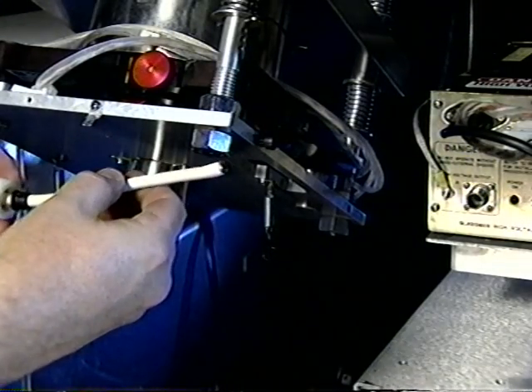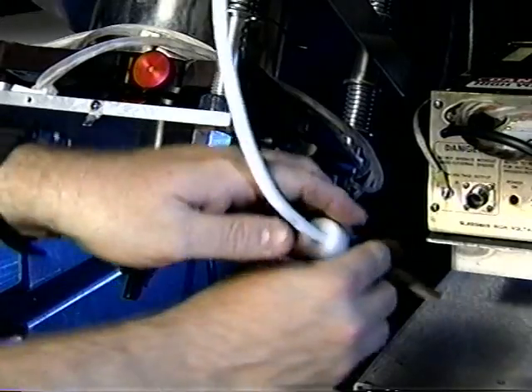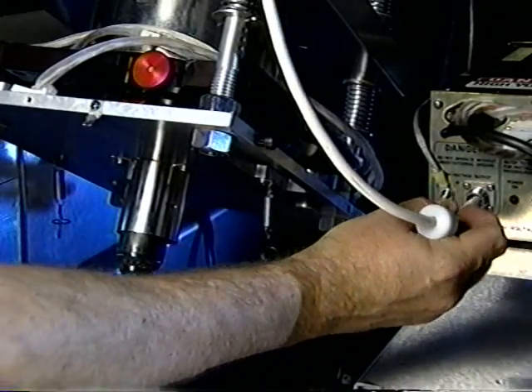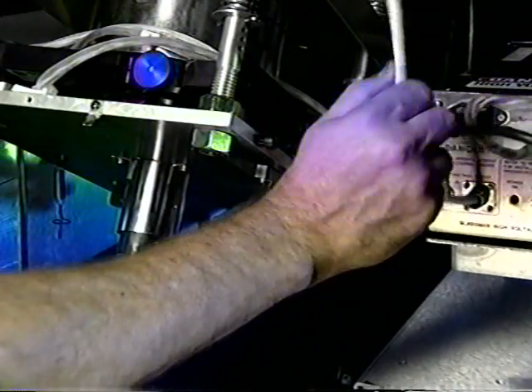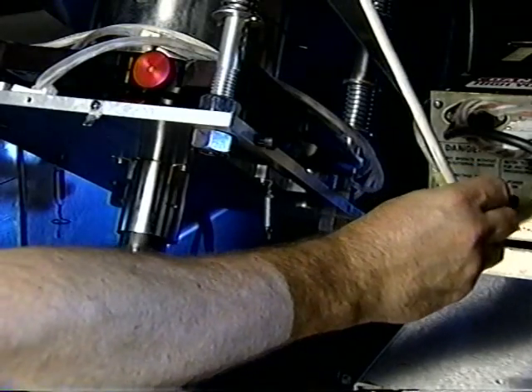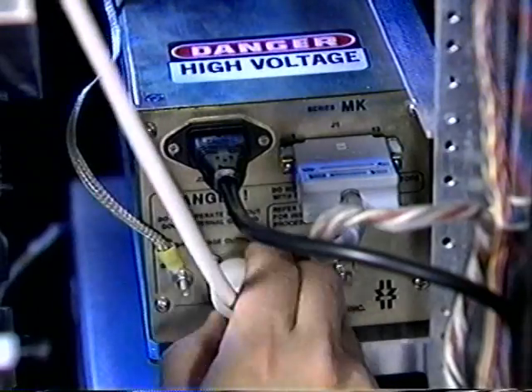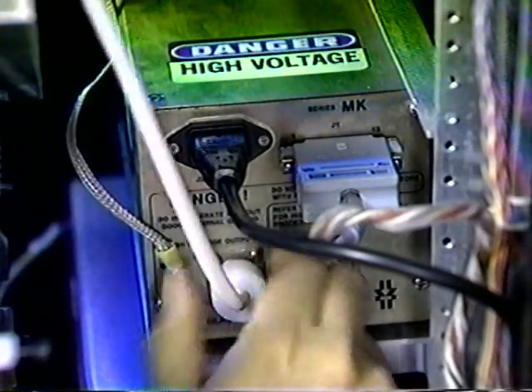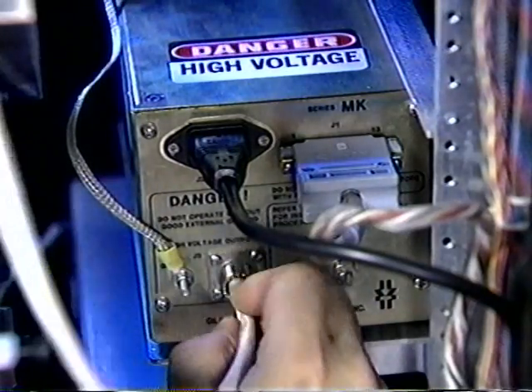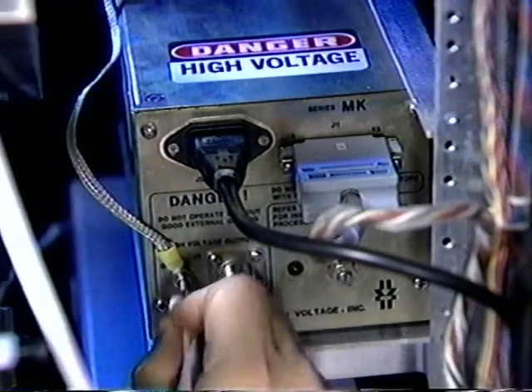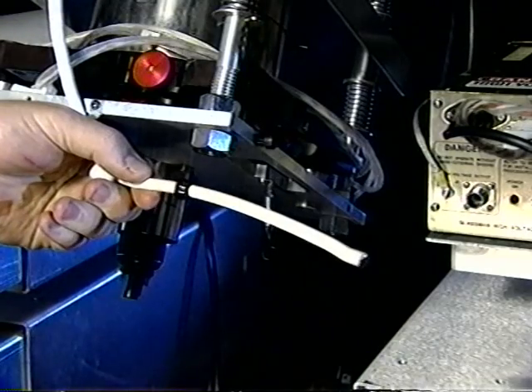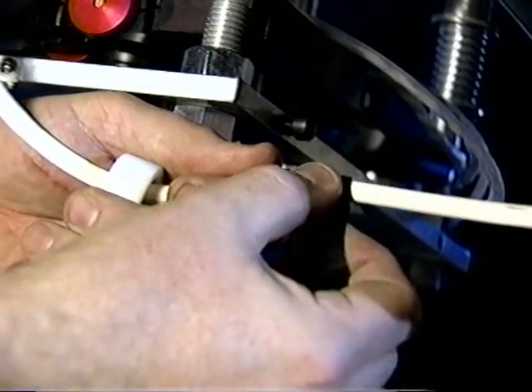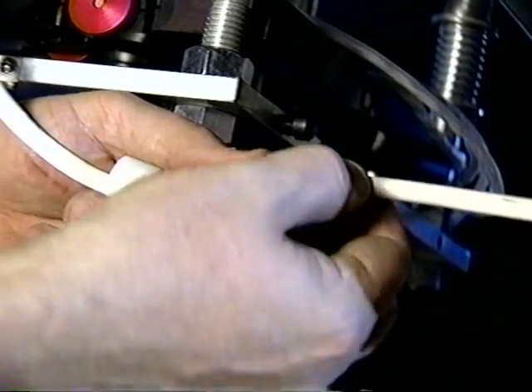Insert the anode lead into the high voltage power supply as far as it will go. You will feel the lead bottom out against a spring. Push the grommet into the power supply socket. Screw the nylon nut on and see if the anode lead stays put. If it doesn't, pull the anode lead out without disturbing the position of the grommet on the cable. Cut a 3-inch piece of tape and wrap it around the anode lead just above the grommet location. This will prevent the lead from sliding out.